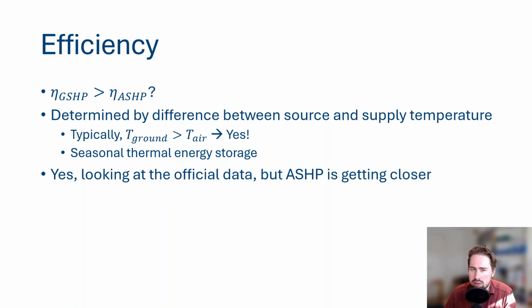Also, if you look at the official data, you look at technical documentation, typically your ground source heat pump has a higher efficiency, but what we see is that over the years, air source heat pumps are getting closer to the efficiency. And that's because, of course, thermodynamically, the refrigeration cycle and the compression cycle, it has the same efficiency. It's the same physics. So in theory, it should reach the same efficiency. The reason why it's not is because a ground source heat pump is circulating a fluid, and the fluid has to give away the heat to a refrigeration cycle, and that is a little bit easier than getting energy out of the air. So it's not so much the efficiency of the refrigeration cycle itself, it's more related to the way the energy is given to the refrigeration cycle. But that being said, air source heat pumps are getting closer to the official data for the efficiency.